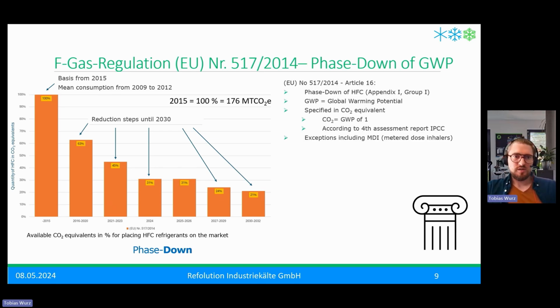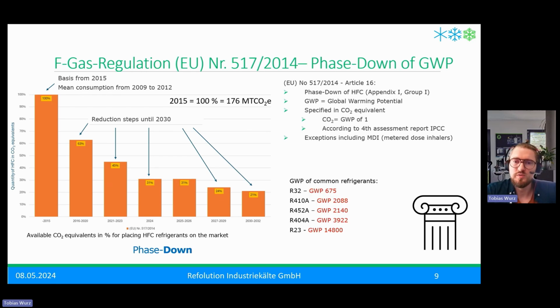Just some short points to this. It's the phase down of HFCs, so hydrofluorocarbons from Annex 1. So it's not concerning the HFOs or natural refrigerants. The phase down is based on the GWP. So if you have a refrigerant like R32, it has a medium GWP of 675. Then on the market you can place a lot of R32, but for example with a higher GWP like R410A, you can only place a third of this refrigerant on the market.